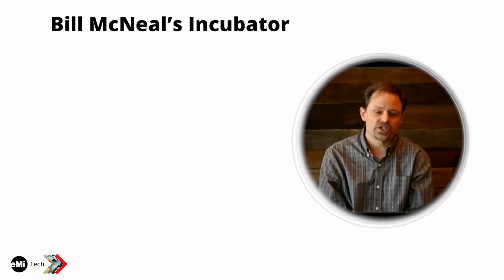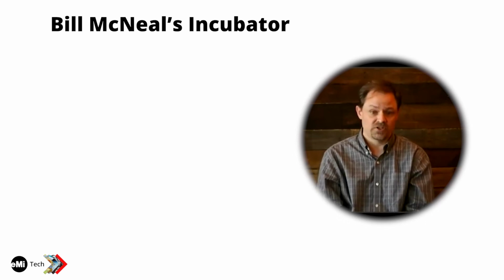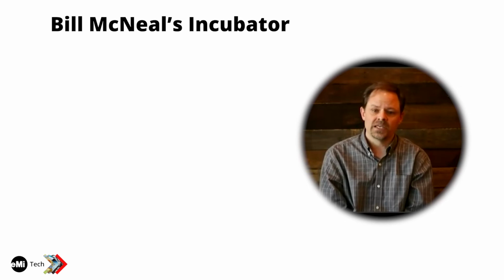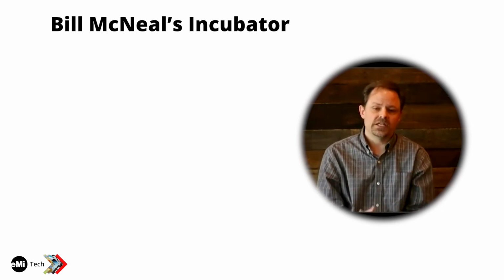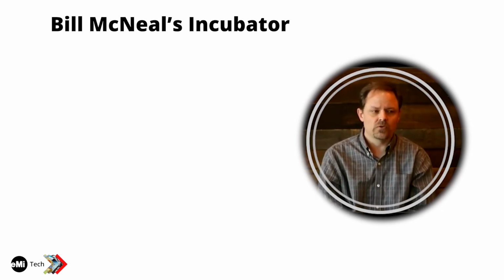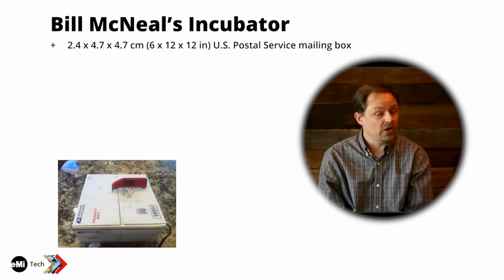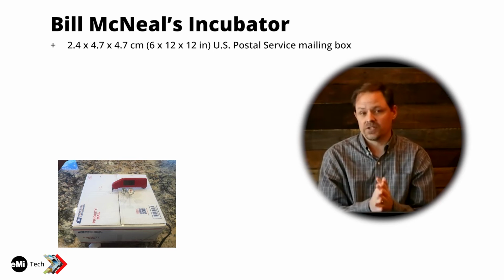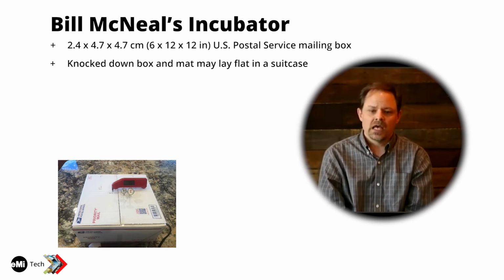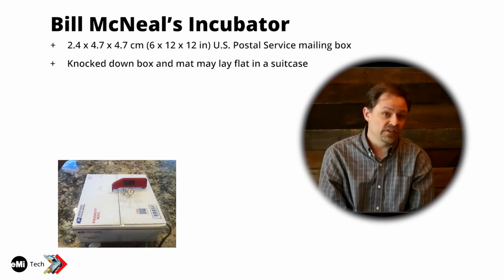So I wanted to mention a low-cost home-built incubator that was developed by Bill McNeil. He's an EMI volunteer, and he had, I think, a great idea. So what he does is he just takes a U.S. Postal Service priority mail box, which you can get at the post office here in the U.S. for free. You can lay it flat in your luggage when you travel. And so that forms the shell of the incubator.